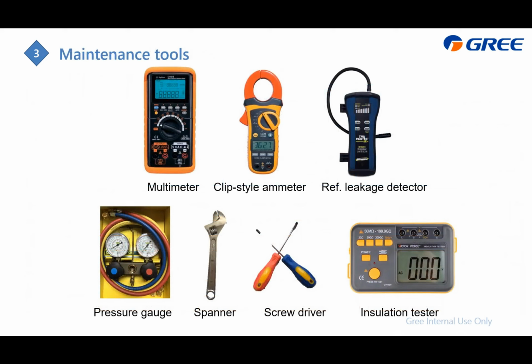This is the maintenance tools you may use during the troubleshooting. And this is the multimeter. And this is the clip-style ammeter to check the current. And this is the refrigerant leakage detector. And this is the pressure gauge to check the refrigerant system pressure. And also you need to equip with this spanner and screwdriver. And this isolation tester is to check the compressor resistance. Later I will introduce how to use it.